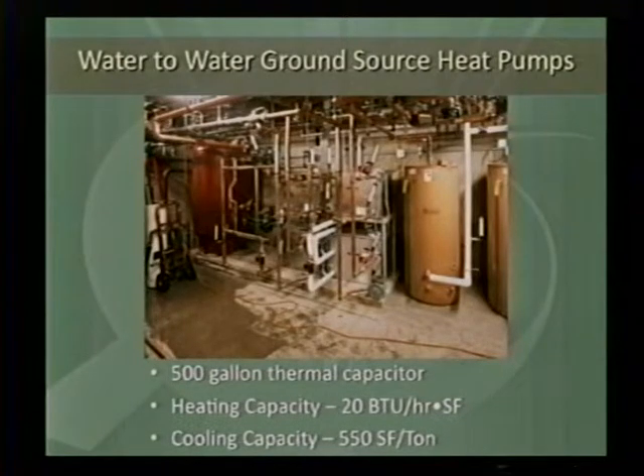The water-to-water ground source heat pump meant that we were using a central system. We had three 6-ton heat pumps all tied in parallel together to basically provide hot water for the heating coil and the floor slabs, and chilled water for the cooling coil in the summer, and the slabs. Now, we might have a very small load in one of the radiant zones in the floor slab, and we wouldn't want to turn on one, two, or three 6-ton heat pumps for what might be a half-ton load at a particular point in time. Heat pumps you really want to balance very well to the load that they're carrying.